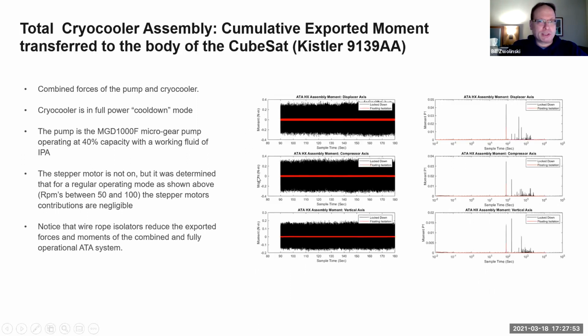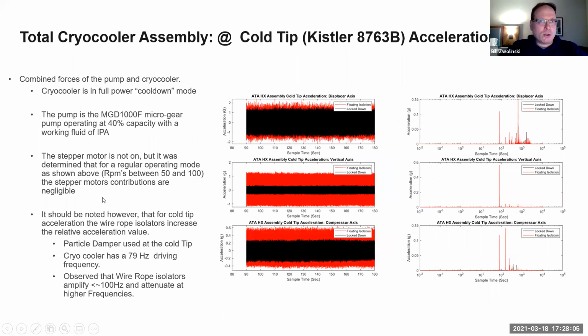And certainly that was forces, and this is for moments, and you see generally the same trend where the vibration is mitigated by use of the wire rope isolators. This one here is actually at the cold tip of the cryocooler assembly, using the accelerometer. What you see here is basically the opposite. You see that the actual vibration is more at the cold tip end in this case, and we traced that back to the wire rope isolators actually amplifying below 100 hertz. And out at the cold tip, if you could see the frequency response here to the right, there's actually a significant harmonic right around 90 hertz. So you definitely have more development to be done on the wire rope isolators for sure.